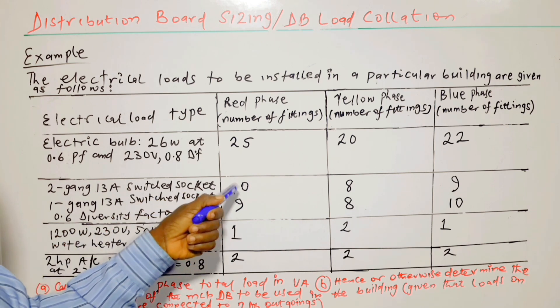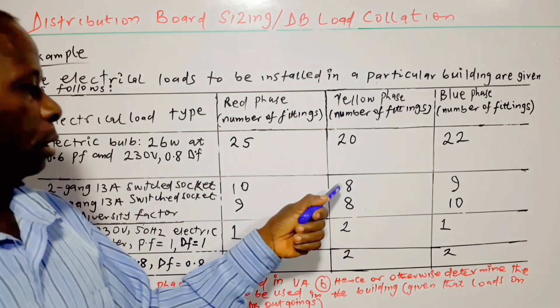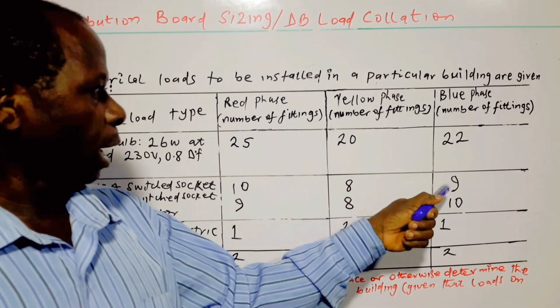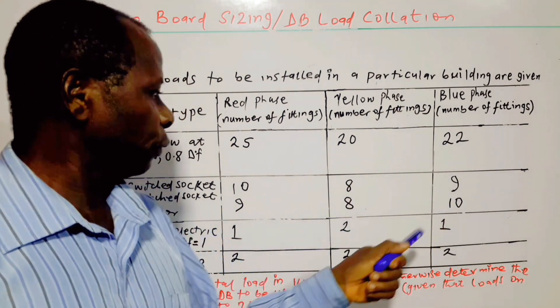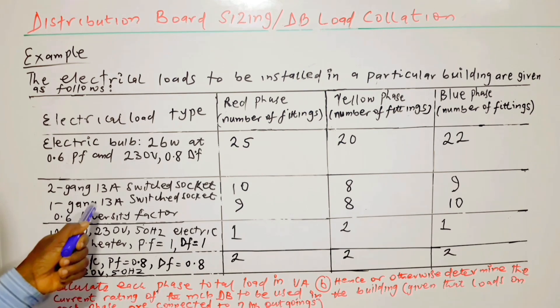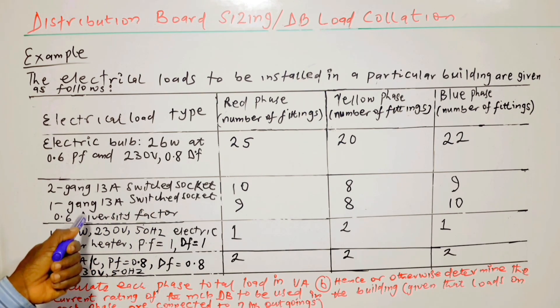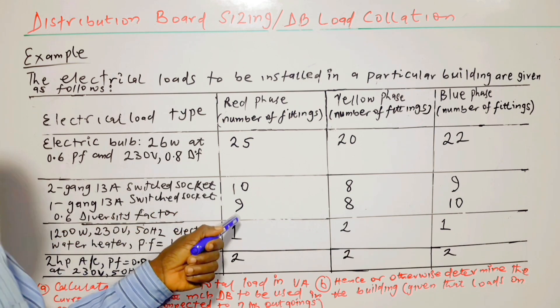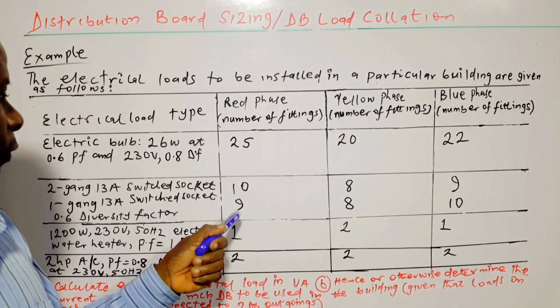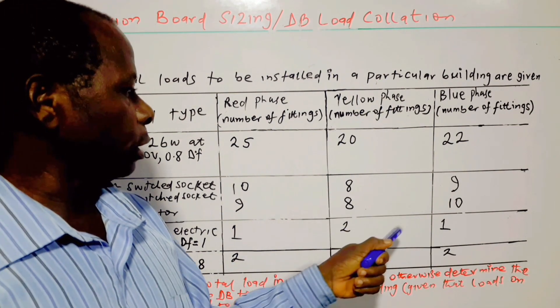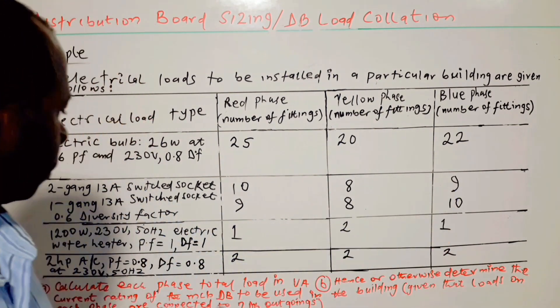For the 2-gang 13A switched socket circuits, we have 10 on red phase, 8 on yellow phase, and 9 on blue phase. Then we have 1-gang 13A switched socket circuits at 0.6 diversity factor as well. We have 9 on red phase, 8 on yellow phase, and 10 on blue phase.